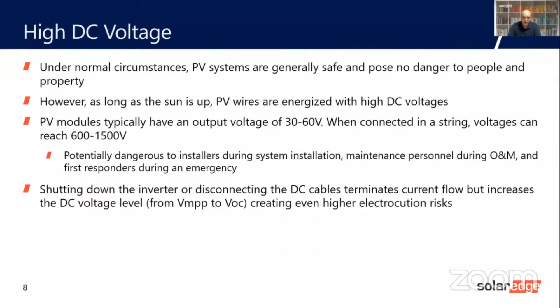Shutting down the inverter or disconnecting the DC cables simply terminates current flow, but in actual fact, it further increases the DC voltage on the DC lines. The modules move from what we call VMPP to VOC, and that creates higher voltage and even higher electrocution risks within the PV system.